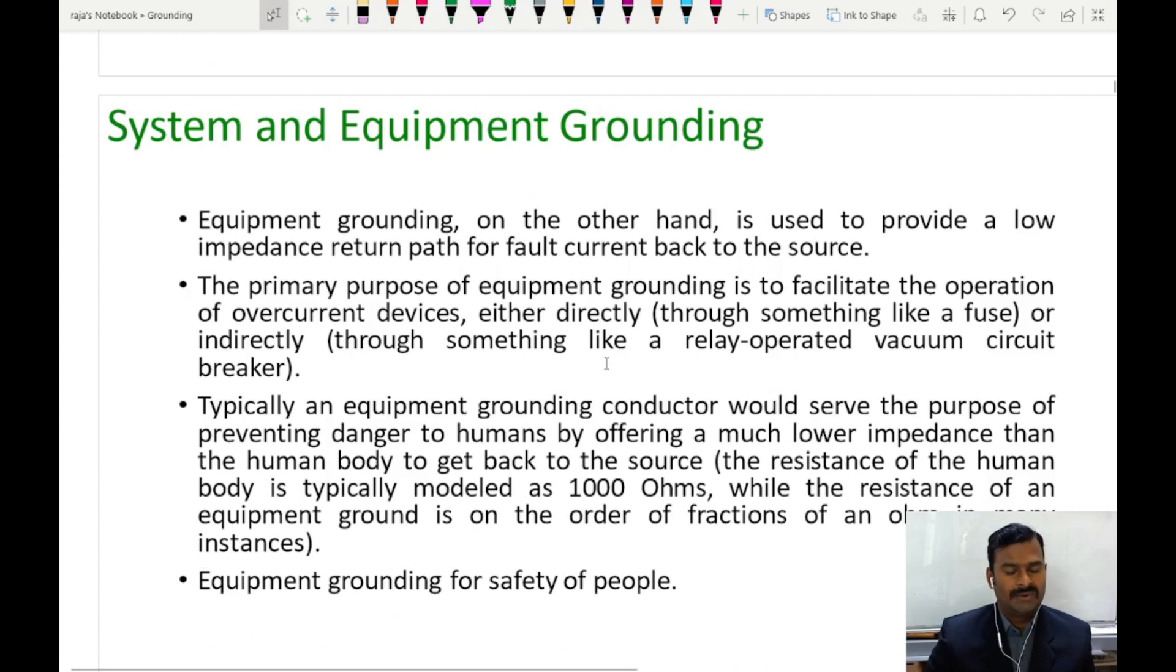Let us understand now what is equipment grounding. Equipment grounding is done to protect the human being from ground fault. For example, you say there is a connection between the line conductor and the machine body. The leakage current would be available in the machine cover and when the human comes in contact with that machine, it starts discharging through him.